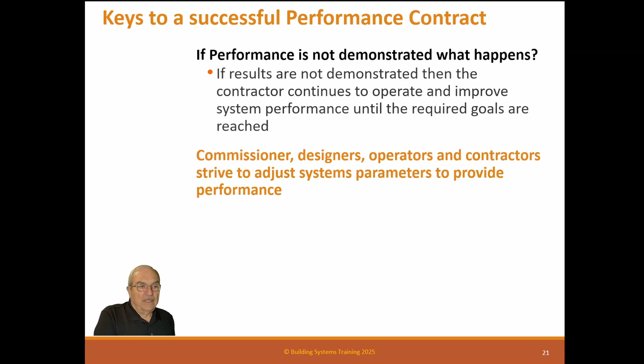The commissioners, the designers, the operators, and contractors strive to adjust system parameters to provide performance. So we'll go in and do what we have to make that actually work. Demonstrated performance for any 2 measurement periods during the cooling season and 2 measurement periods during the heating season will complete the contract. So we have 12 months to prove that 2 months in summer and 2 months in winter work. If those 4 months show it works, then we're done. We don't have to wait a whole year, but we need 2 months because 1 month could be just a fluke. We don't want to do that.